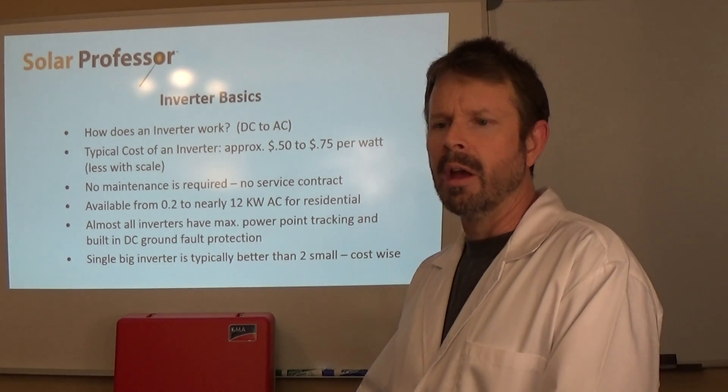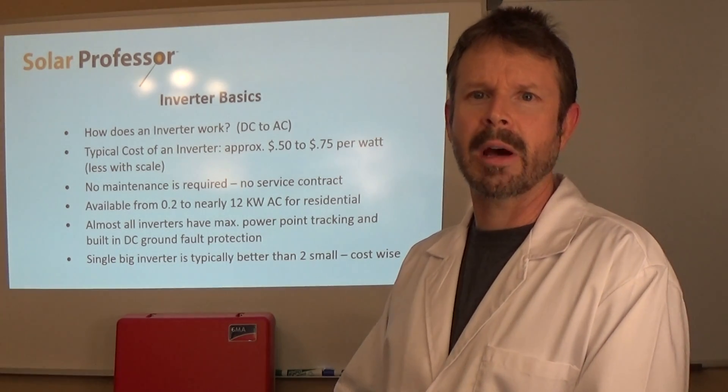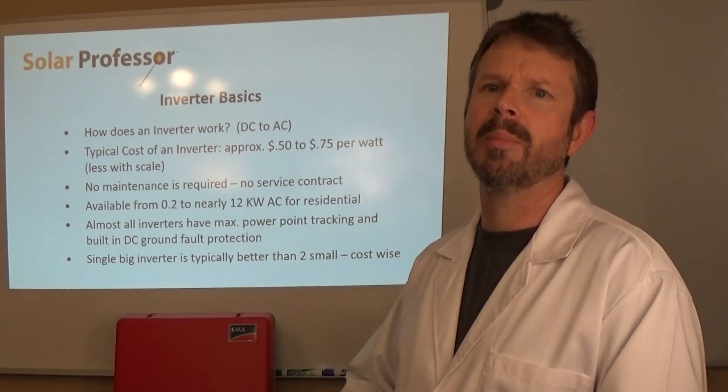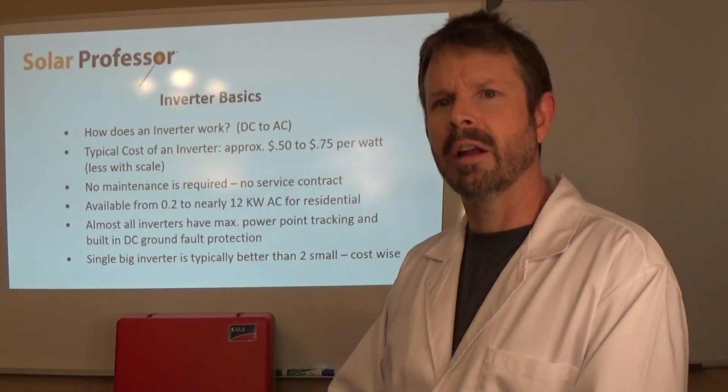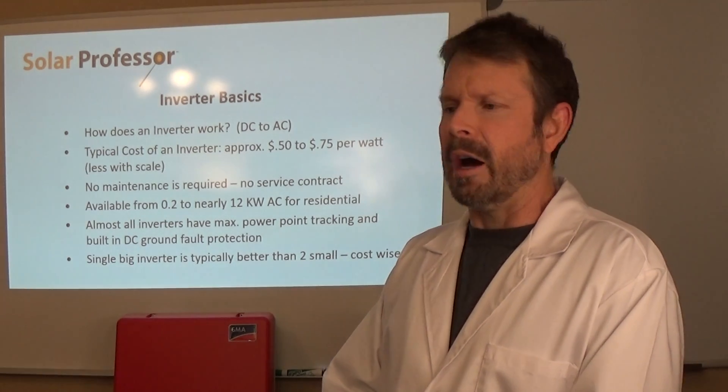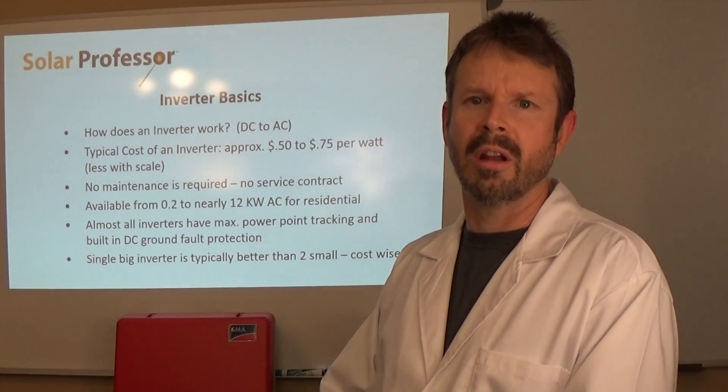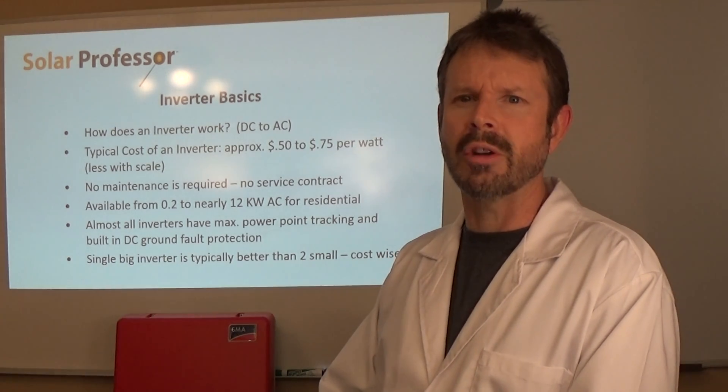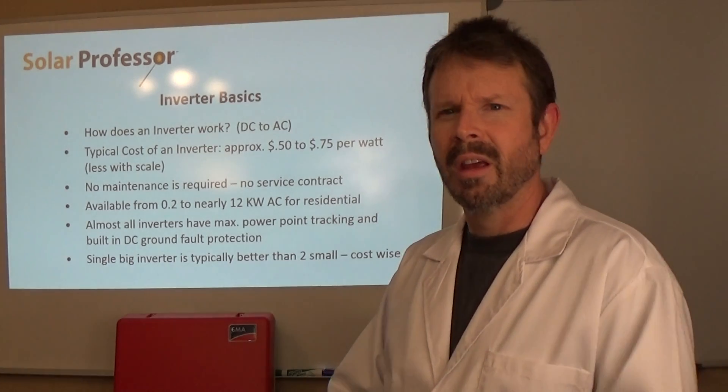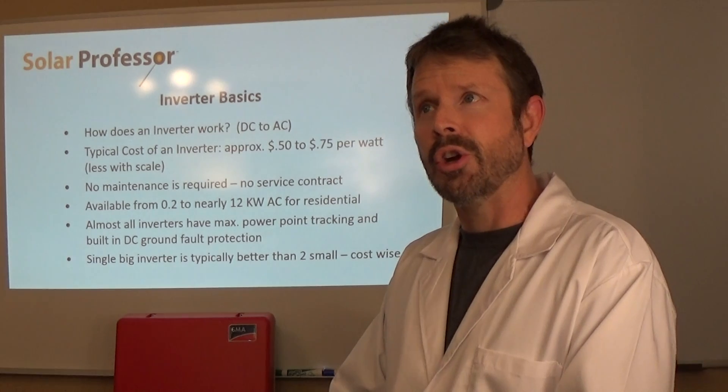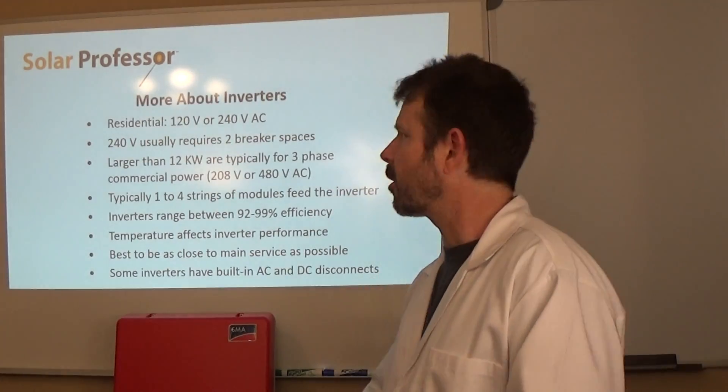Almost all inverters have maximum powerpoint tracking and built-in DC ground fault protection. Grounding and ground faults are super important when we're installing. MPPT, what that does is the inverter being an electronic device wants to find the sweet spot in the IV curve and stay there. An MPPT inverter will try to lock into the knee of that IV curve for as long as it can depending on sun conditions. That's really what the rudimentary meaning of maximum powerpoint tracking is. Single inverter is typically better than two small cost wise.